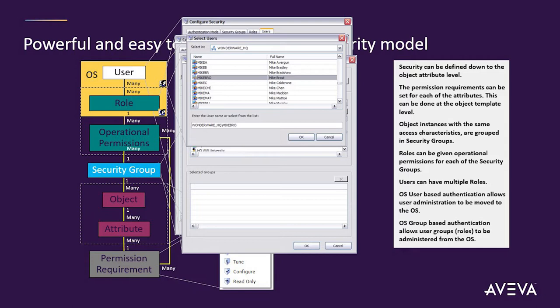It's a very easy security model to maintain because I'm not maintaining it at a thousand different touchpoints — I'm maintaining it at one spot, at the template level. I can put systems into groups, create roles, and have those roles come in from Active Directory or my domain controller. Ninety percent of our systems use this group-based security because I don't want to change my SCADA system every time somebody changes jobs — I want IT or HR to manage what roles they're supposed to have.